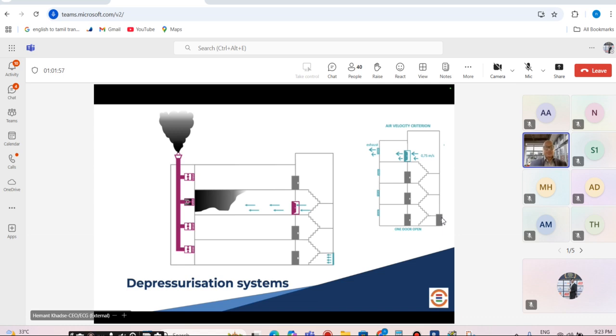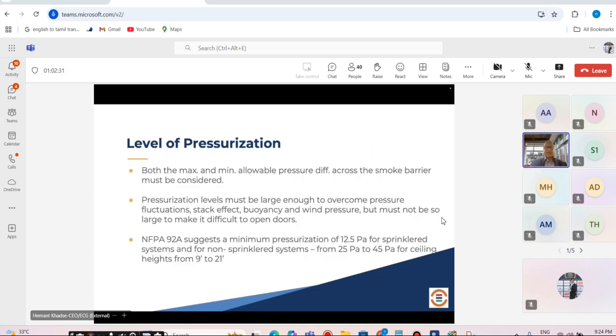When you use exhaust systems, how your makeup air is expected, with the door openings or mechanically, so that you have effective pressurization or negative pressurization systems in the building, because you not only have to take the negative pressure, you also have to have makeup air to complement that exhaust system, so that it becomes the driving effect. So the level of pressurization is addressed by NFPA 92 very well. You can probably take the basis of codes. IBC also has addressed multiple chapters where you can get the basis developed.